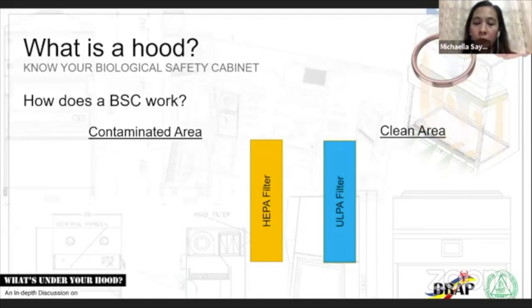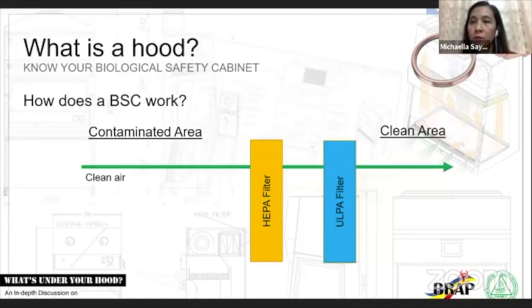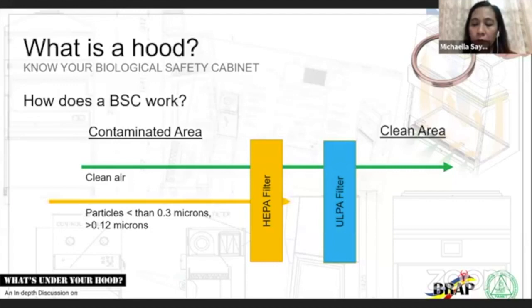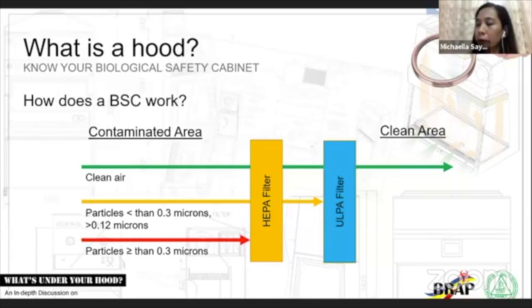Now, this is just a simple animation of how it works. So if you're clean air, you pass through both filters, HEPA and ULPA. Now, if you're a particle that is smaller than 0.3 microns but greater than 0.12 microns, you get stuck in your ULPA filter. Now, if you're bigger than that, you get stuck by your HEPA filters, right?